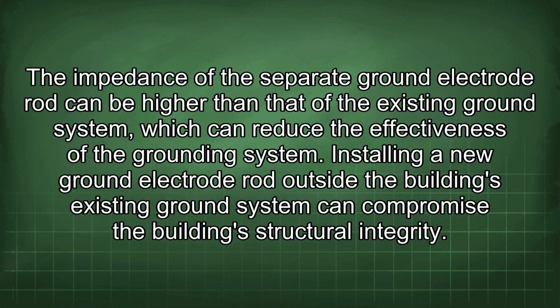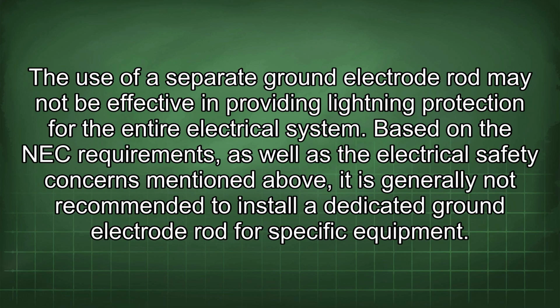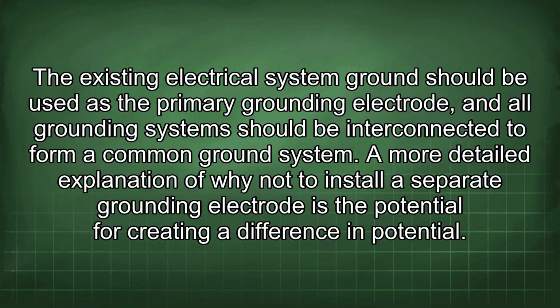Installing a new ground electrode rod outside the building's existing ground system can compromise the building's structural integrity. The use of a separate ground electrode rod may not be effective in providing lightning protection for the entire electrical system. Based on the NEC requirements, as well as the electrical safety concerns mentioned above, it is generally not recommended to install a dedicated ground electrode rod for specific equipment. The existing electrical system ground should be used as the primary grounding electrode, and all grounding systems should be interconnected to form a common ground system.